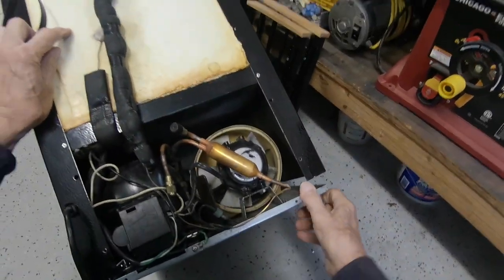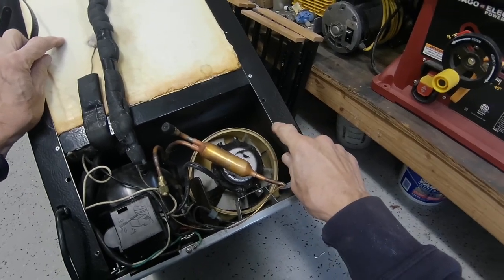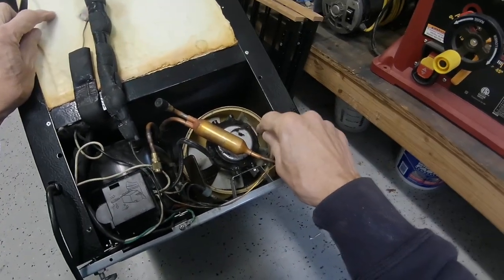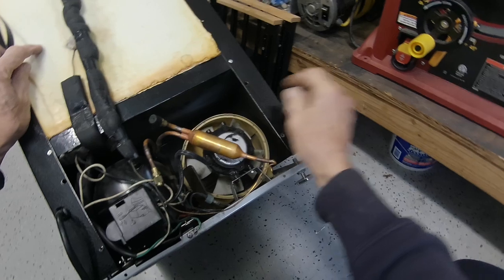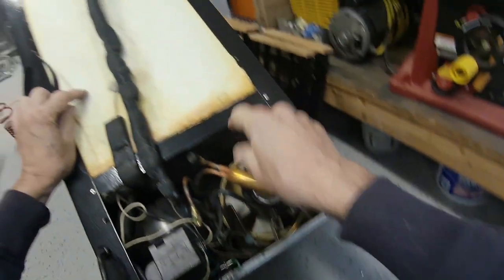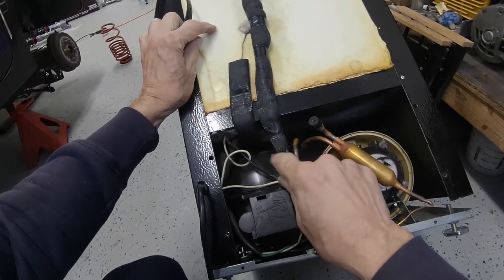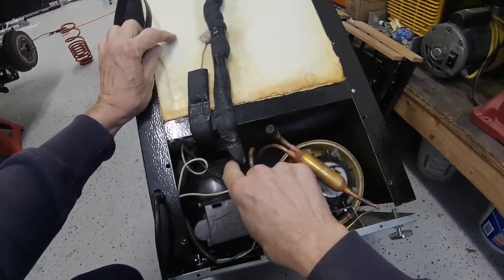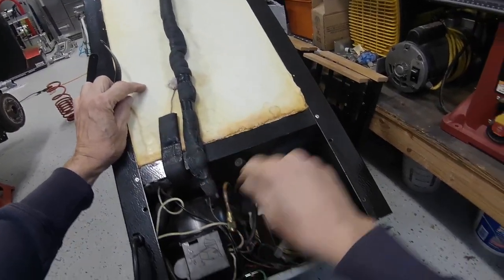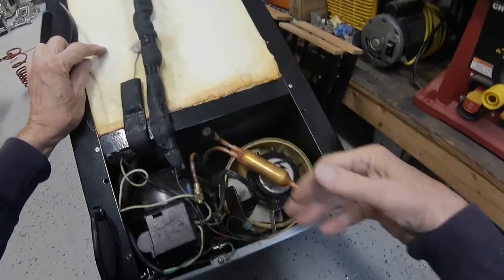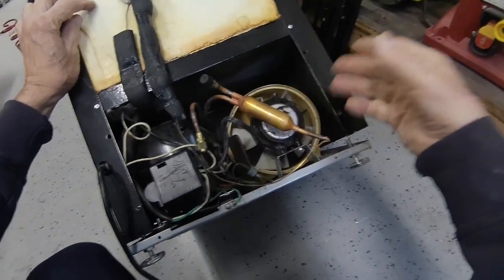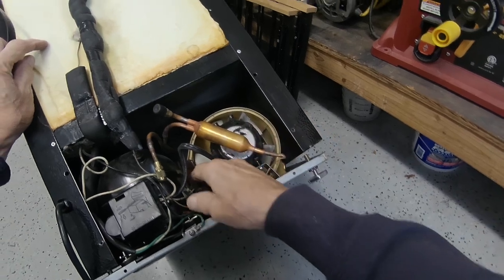This is about as far off you can get the cabinet to get in there to work on this fan and the shroud. The fan is held in on the bottom with these 4 screws. Unless you take all the Freon out and disconnect the heat exchanger you can separate the whole cabinet, but we don't want to do that. We just want to change that bent up shroud.